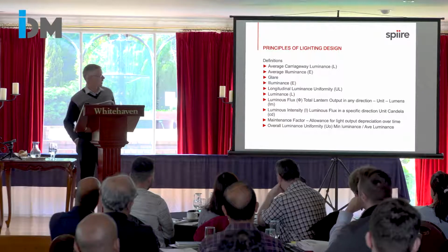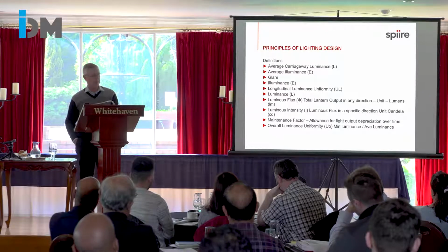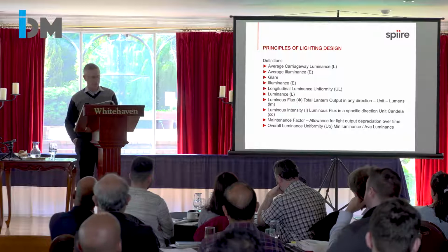Now that LED lights have been introduced, maintenance factors technically could be reduced, given that the LED, the way it's designed, will maintain a consistent output throughout its life, whereas the older discharge lanterns and fluoros, etc., depreciated over time.